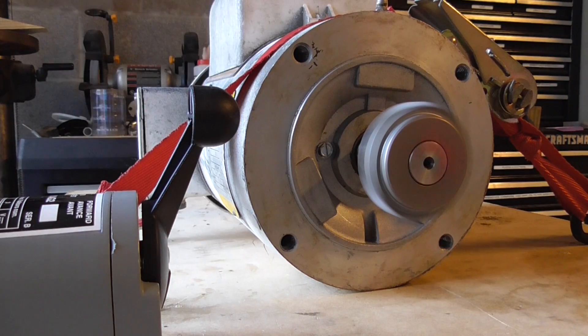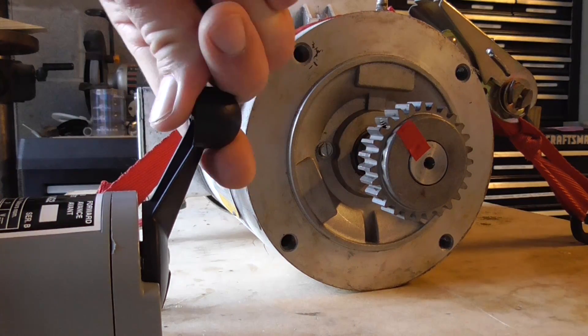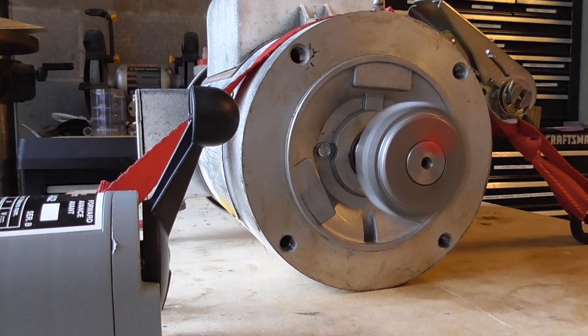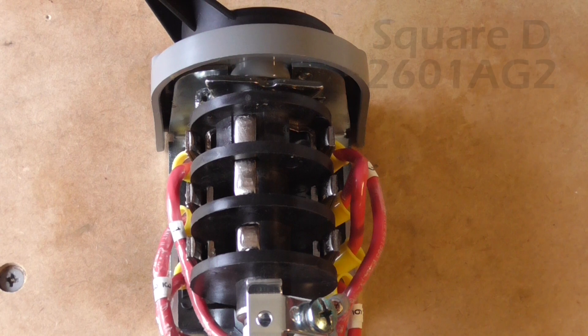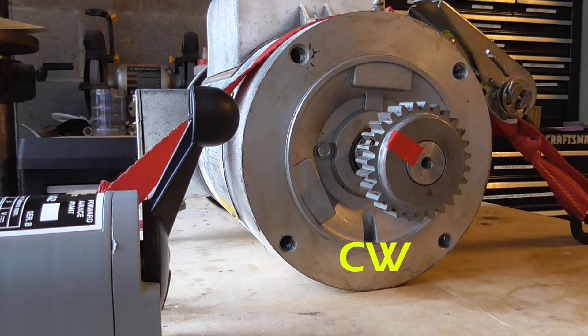The motor is wired to the drum switch. Move the handle to reverse and the motor runs counterclockwise. I'll fast forward as it stops. Move the handle to forward and the motor runs clockwise. I'll fast forward again. So I've got a single phase 230 volt AC motor with three separate windings wired to a Square D 2601AG2 drum switch. It allows you to easily operate the motor in the clockwise or counterclockwise directions.